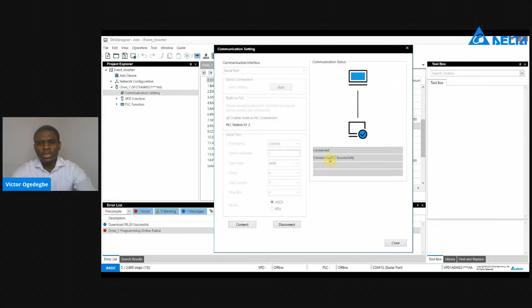So for just a test, let's select serial port, because I also like to connect to the internal PLC and the inverter at the same time. Start. So I'm scanning for the drive. In a moment, it will be connected. You see, the drive is connected, and the internal PLC of the drive is also connected as well. Easy connection for upload and download. Now let's try the download feature now that we are connected. Now we're going to go to the download button.